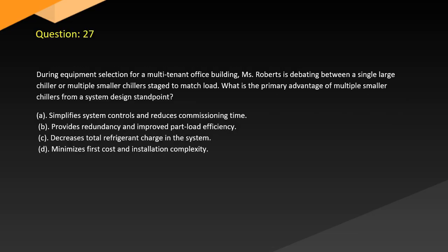Question 27. During equipment selection for a multi-tenant office building, Roberts is debating between a single large chiller or multiple smaller chillers staged to match load. What is the primary advantage of multiple smaller chillers from a system design standpoint? A. Simplifies system controls and reduces commissioning time. B. Provides redundancy and improved part load efficiency. C. Decreases total refrigerant charge in the system. D. Minimizes first cost and installation complexity.